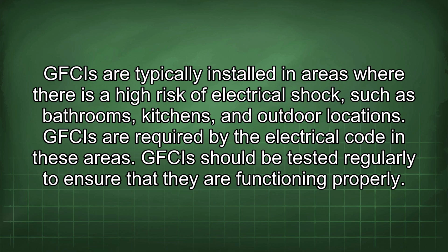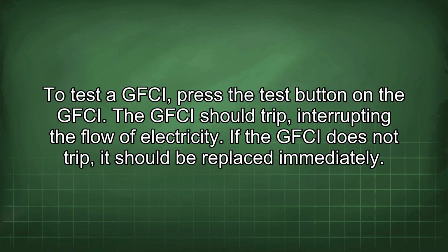GFCIs should be tested regularly to ensure that they are functioning properly. To test a GFCI, press the test button on the GFCI. The GFCI should trip, interrupting the flow of electricity. If the GFCI does not trip, it should be replaced immediately.